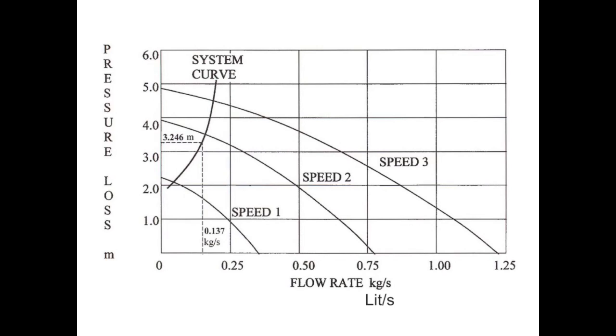Here we have a performance characteristics chart of a fixed rate pump with three different speeds. The vertical axis here is given as a function of pressure loss in meters, and the horizontal axis is given as a function of flow rates in kilograms per second.